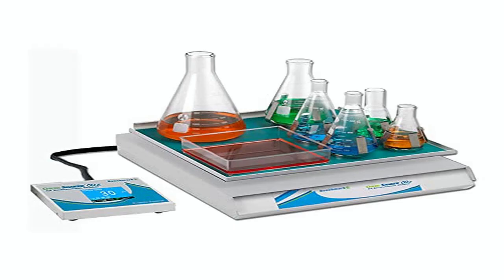The Benchmark Scientific Orbi-Shaker BT4000 is marketed specifically for CO2 incubators, so the first thing I looked at was the physical envelope. At 19 millimeters, 0.75 inches, orbital radius, it offers a gentle, wide sweep that's just enough to keep agar plates or staining trays moving without sloshing liquid out of the wells. The platform itself holds about a kilogram of load, which translates to roughly 10 standard 100 millimeter petri dishes or a few small Erlenmeyer flasks.